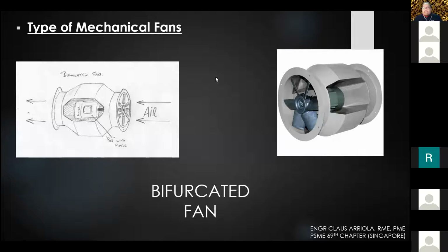Okay, so type of mechanical fans. What do you usually use? A class H fire smoke fan, or a bifurcated fan. Why a bifurcated fan? Because the motor is outside. If it's outside, any fire or very hot smoke coming from or sucked by this fan will not affect the motor or burn the cables inside, so the fan will keep operating continuously. Okay, which is very important.